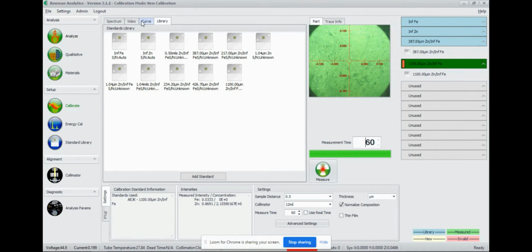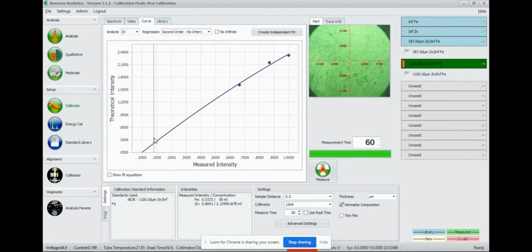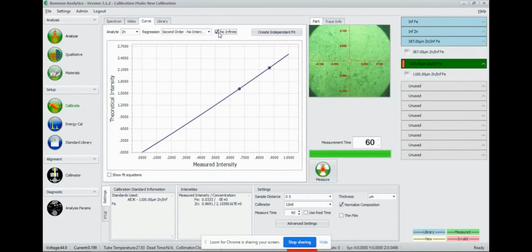Now that we've done that, we're going to check our curve, make sure that that looks okay. Now you can see on this one, our standards aren't exactly on the line. So what I want to do is, in this case, we're going to say no infinite, and that's going to straighten this up, and we're going to catch our 2 points. Those are the two most important things that we want to do, is make sure that our standards that we just measured are on the line. Now that our curve looks good, we are going to save.